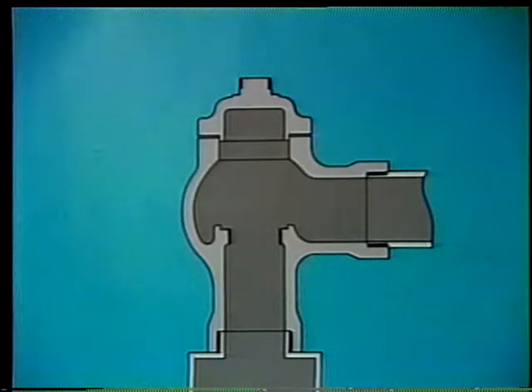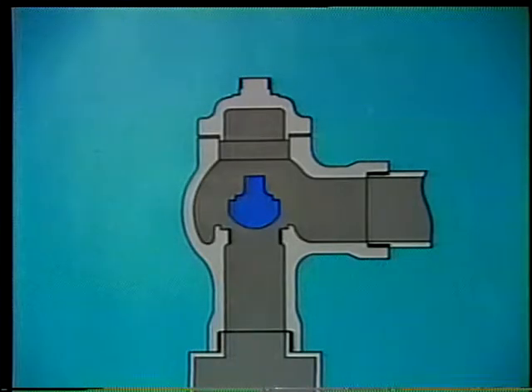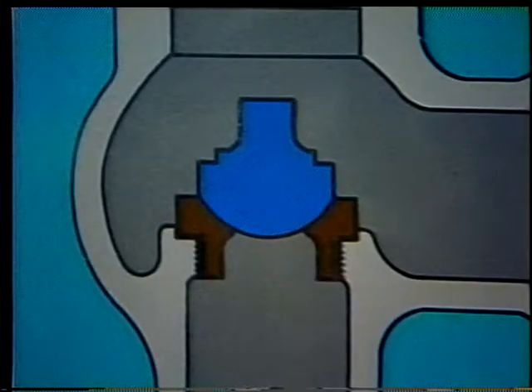When system pressure is normal, the path from the inlet to the outlet is blocked by the disc, also called the plug. Liquid is prevented from leaking around the disc by firm, even contact between the disc and a seat. In some valves, the seat is a permanent part of the valve body. In others, a threaded seat bushing is used. Because it's threaded, a seat bushing can be replaced if necessary.